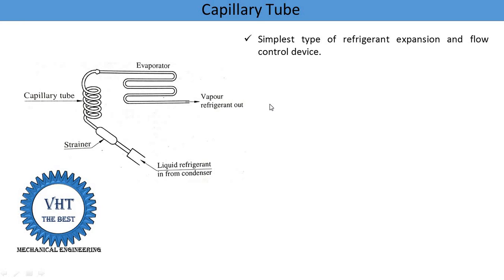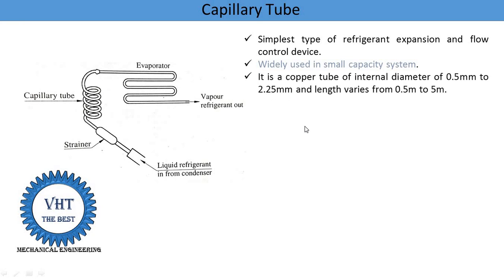This capillary tube is the simplest type of refrigerant expansion device, or flow control device. It is generally constructed from copper and has a very small diameter and certain length. It is widely used in smaller capacity systems — generally used in freezers, refrigerators, air conditioning systems, and water coolers.